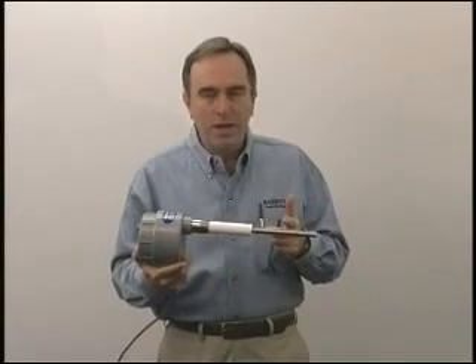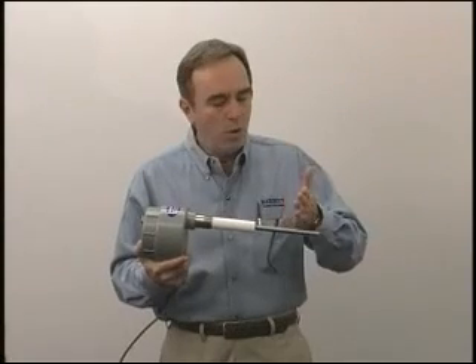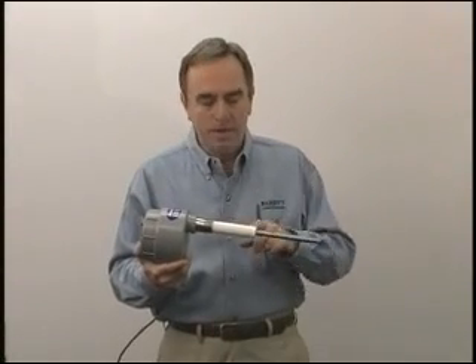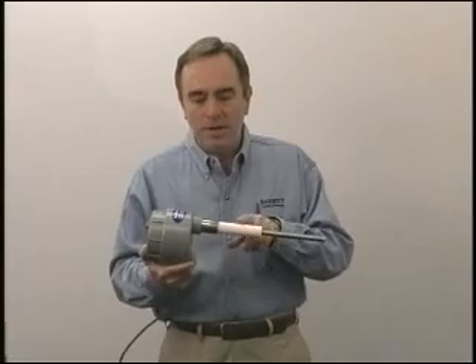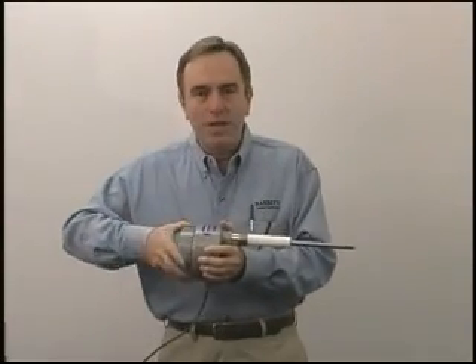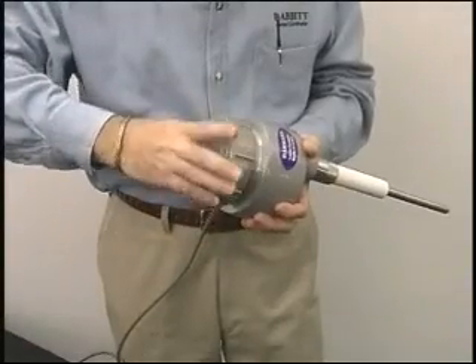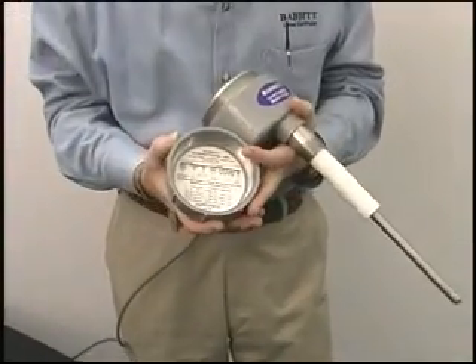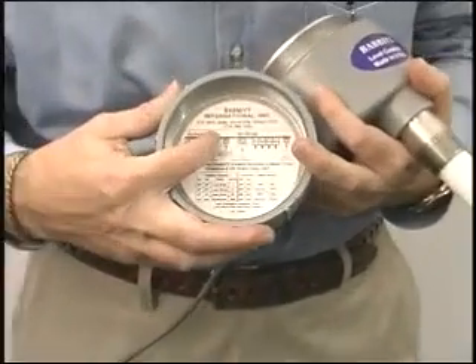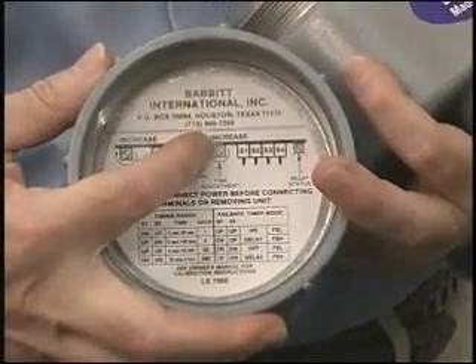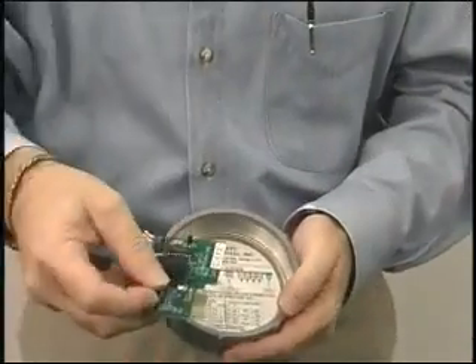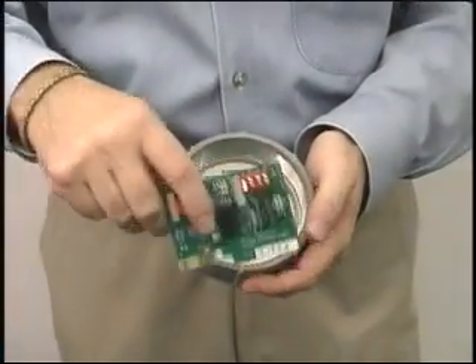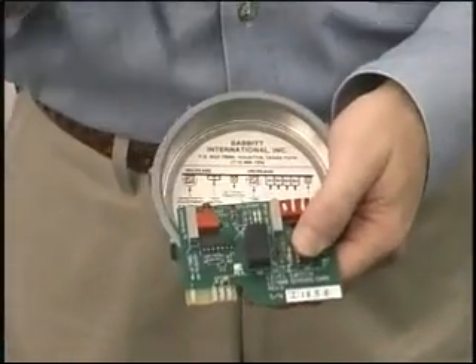The probe is a solid stainless steel rod. You can cut it off with a hacksaw if it's too long, or weld onto it if it's not long enough. The standard insulator is Teflon. The process connection is 3/16 stainless steel. We can make it out of a variety of other materials as well. Explosion-proof housing is standard, and inside the lid we do something that's almost unheard of in the industry, and that is we put our telephone number right there in case you ever have a problem. Also inside the lid is a diagram showing you all the components on the top card edge.